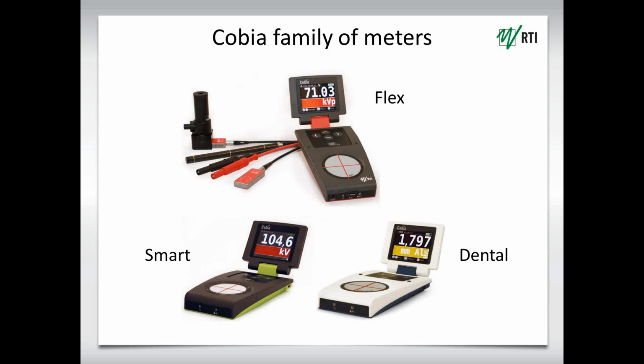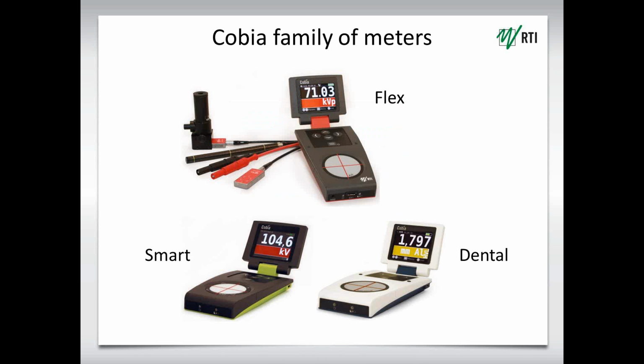If I move on now to the Cobia family of meters, we've got the Cobia Smart down there in the left-hand corner. It measures kV, time, exposure rate, total filtration, and HVL. A real simple meter to use, very accurate, very sensitive. We've got our dental line there as well. And then above, our latest is the Cobia Flex. It can measure with external probes as well. It's got a built-in mA sensor on it, and you can use your light probes, your CT ion chambers, and your CT dose profiler. Very simple to use, with a built-in display.